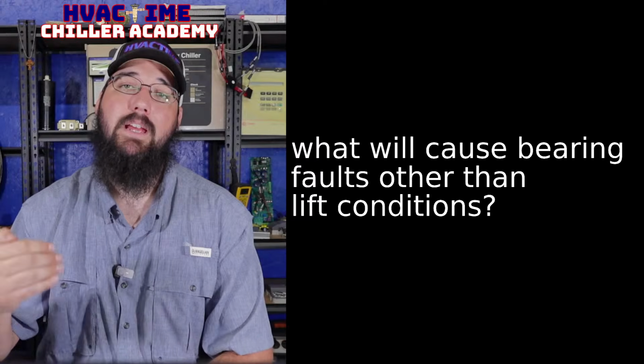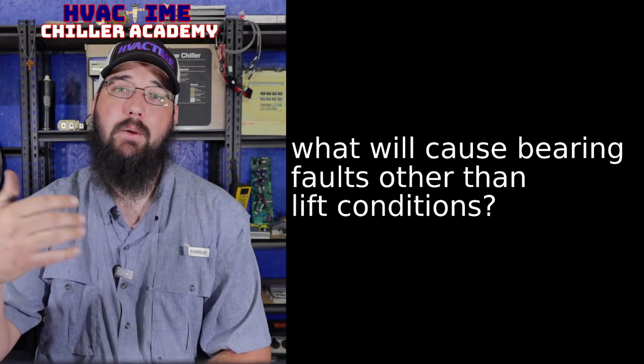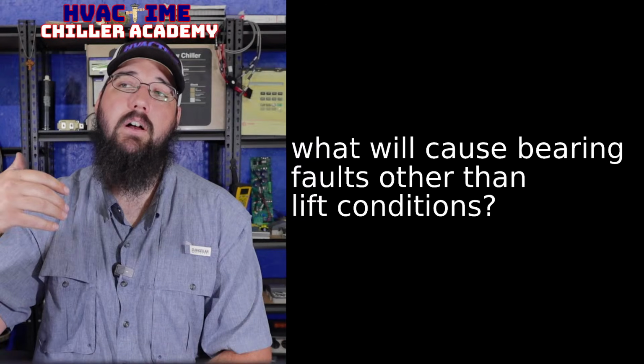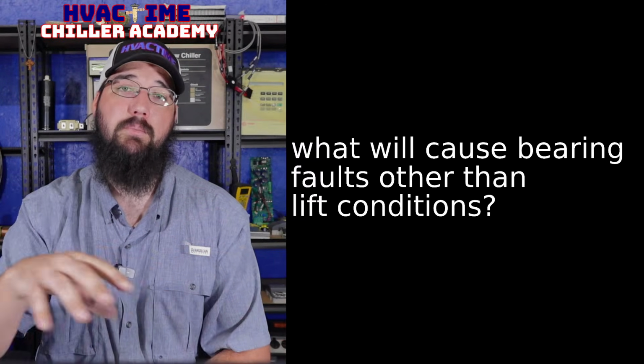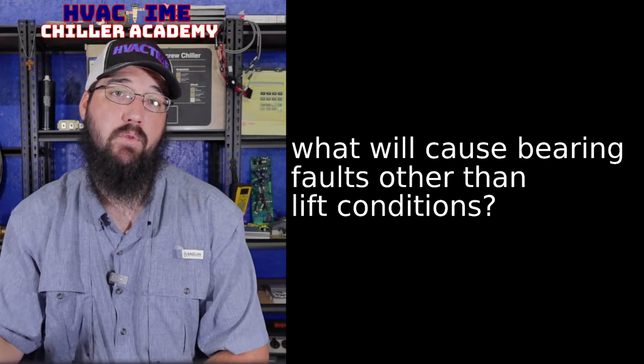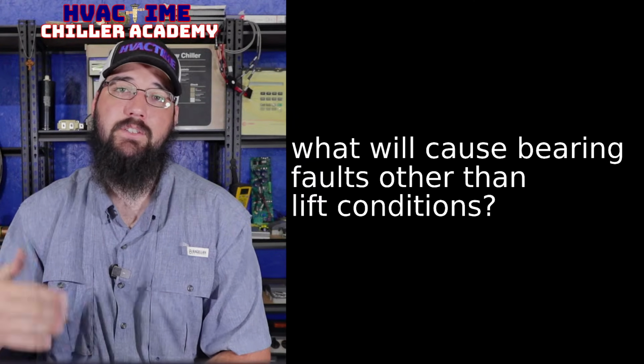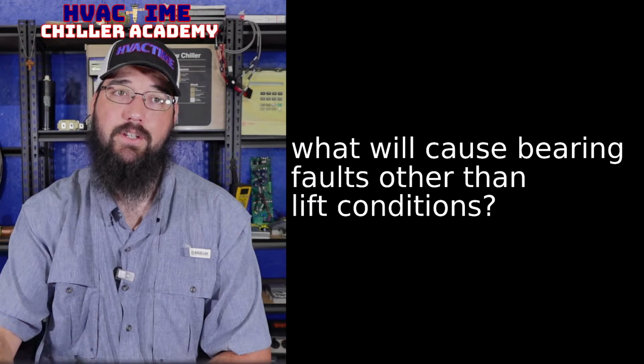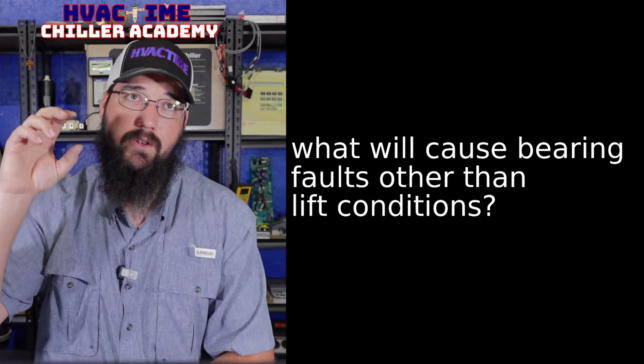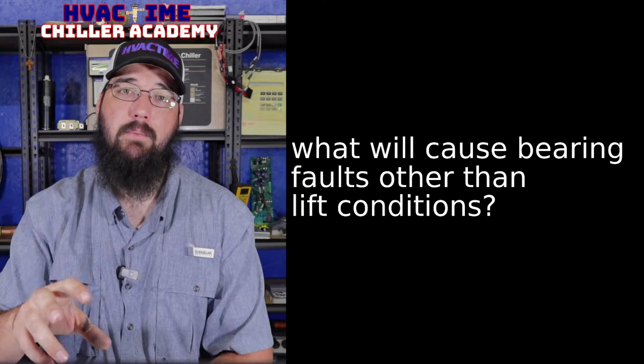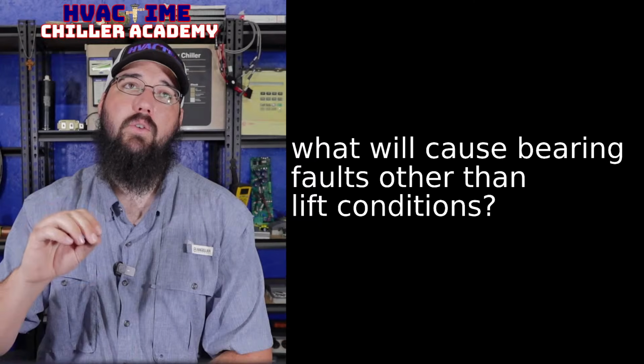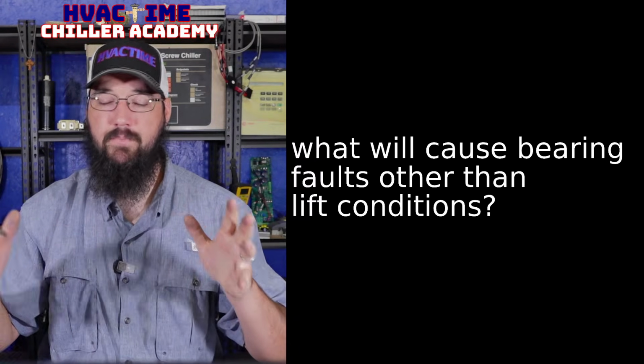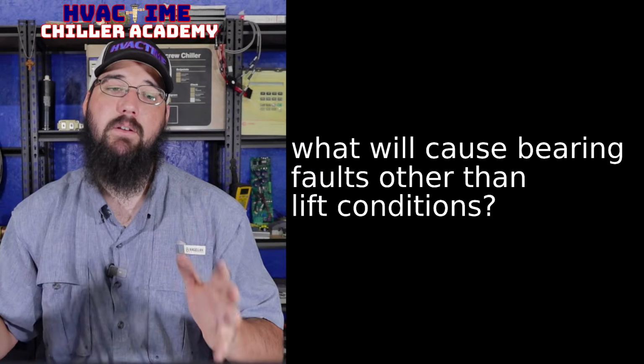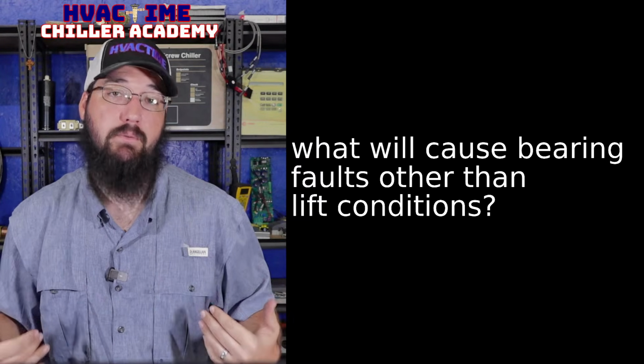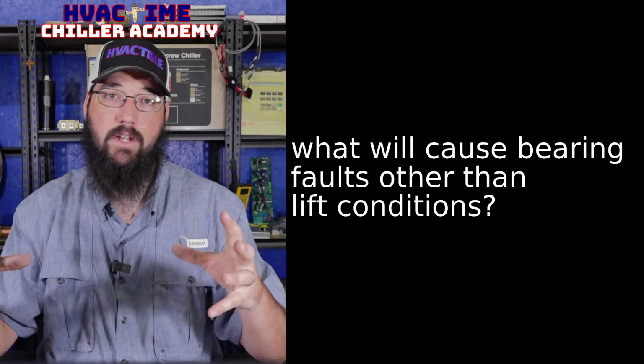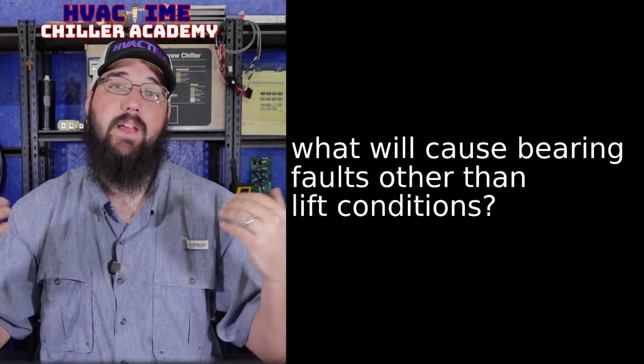If it's in an early state of failure, which would result in, say, occasional bearing faults, or at least it started off as occasional bearing faults. It's now escalated. Maybe it's happening more frequently now, but the inverter is still testing like it's in a good or safe condition. You could still have a problem regardless. Because what we're discussing is, at some point we get to the conversation of, okay, we're having a bearing fault. If it's a bearing, we're having to replace the compressor, right? If one of our radial bearings especially has failed, that compressor is getting replaced.